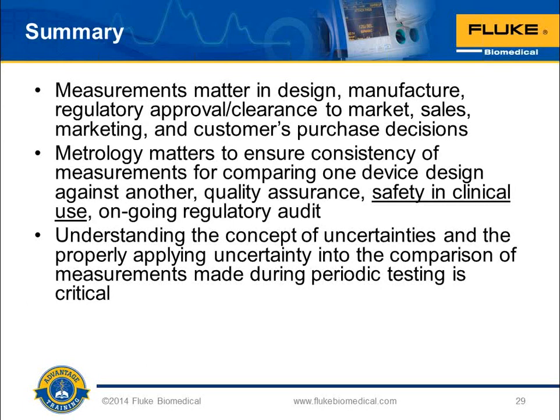So in summary, measurements matter in design, in manufacture, in regulatory approval and clearance to market, in sales, marketing, and customers' purchase decisions about medical devices, and test equipment used to verify this information. Metrology matters to ensure the consistency of these measurements for comparing one device design against another, quality assurance, and safety in clinical use and ongoing regulatory audits. And it's important that we understand the concept of uncertainties and properly apply those uncertainties in the comparison of measurements that we make during periodic testing. These things are really critical, and that's really what we wanted to cover. And if you got that much, you really got the 101 on metrology, which we really want you to have.